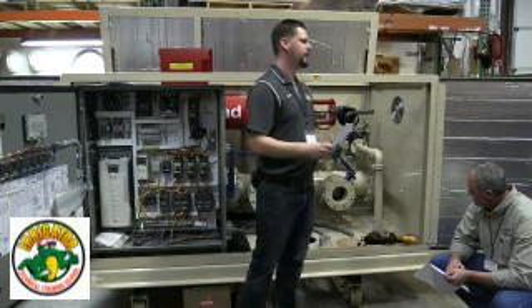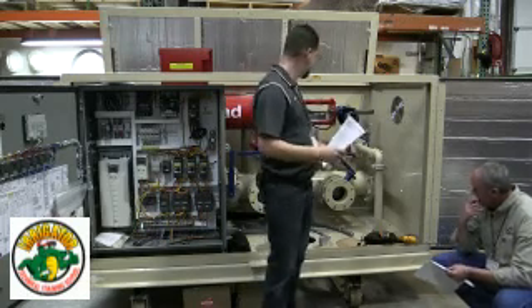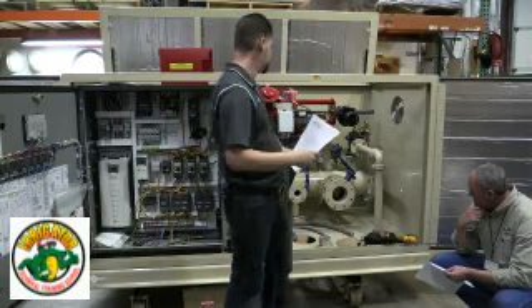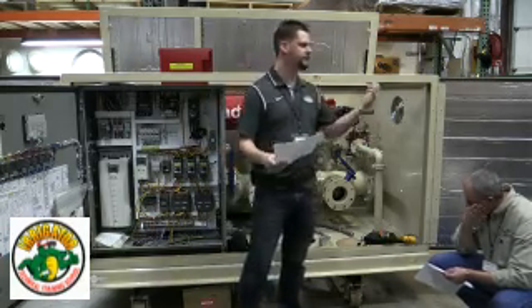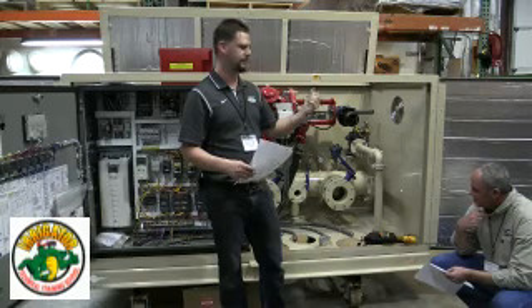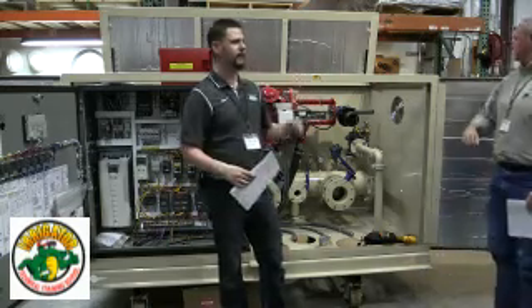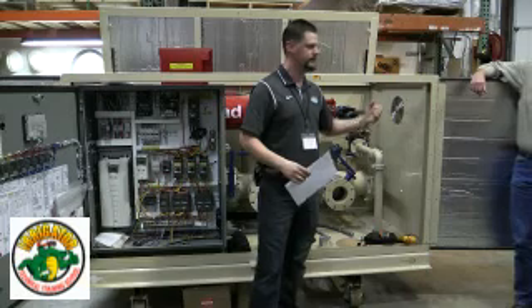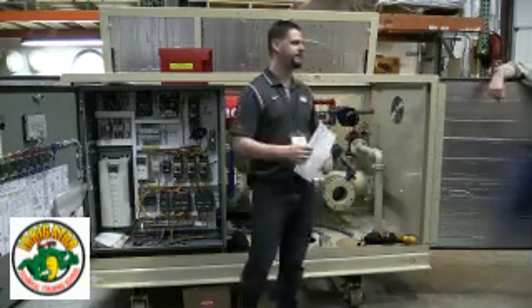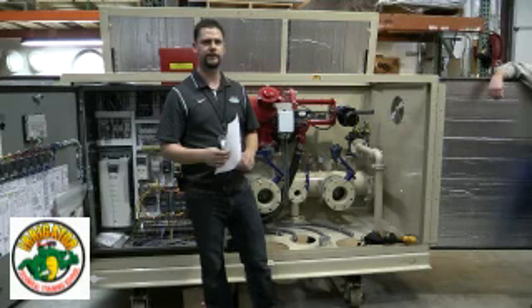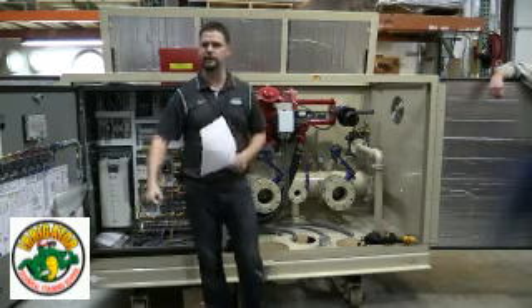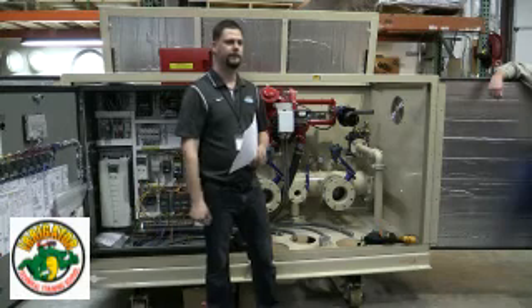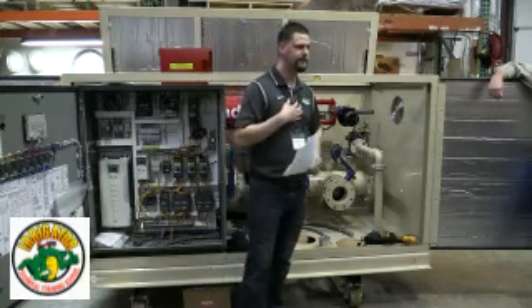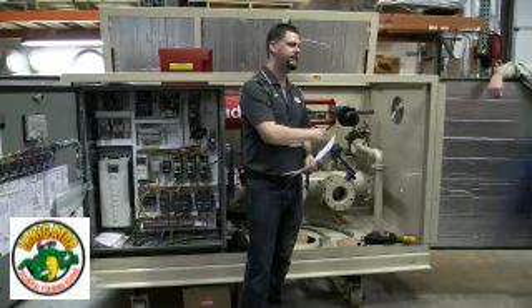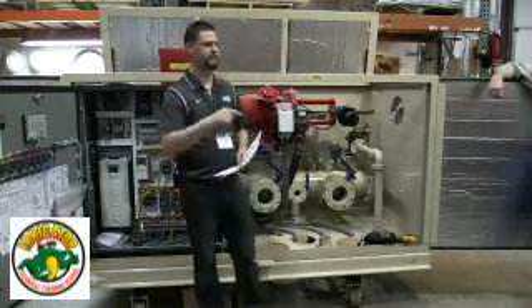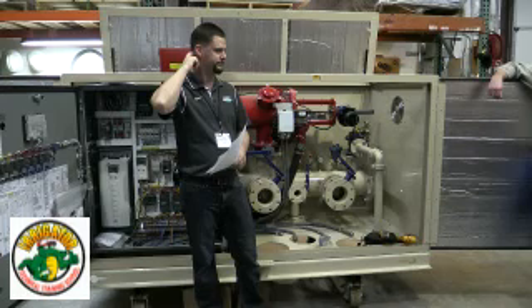But, well, we can imagine that I have a transducer in my hand, fresh off the manifold, bottom of it here. What I do is, with a firm grip, I'll fling the water out of the inside of it. Now, we've had a service tech here that would take a pancake compressor and blow the water out of it. Quite frankly, if it was my pump station in my backyard, I would take that transducer inside where it's not going to freeze for sure with any water in it.